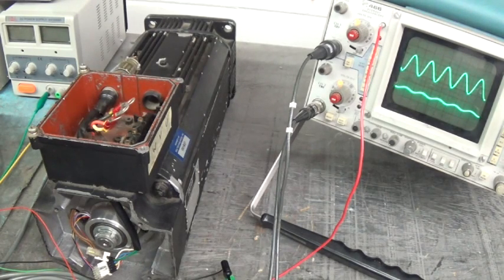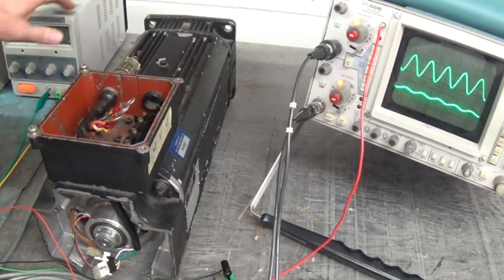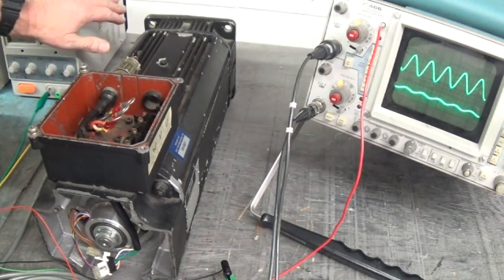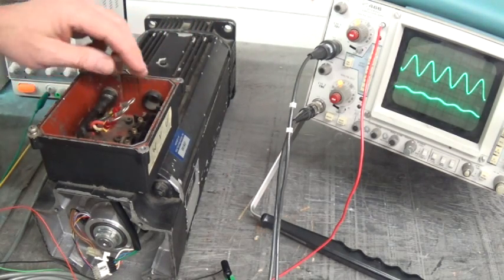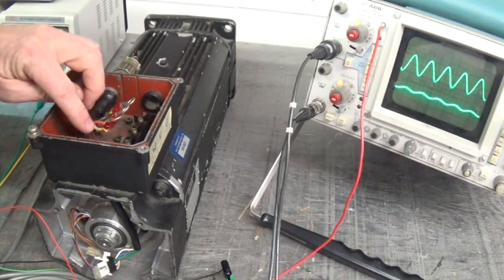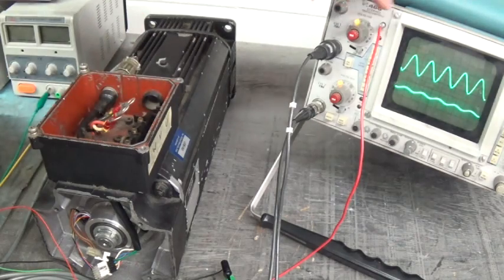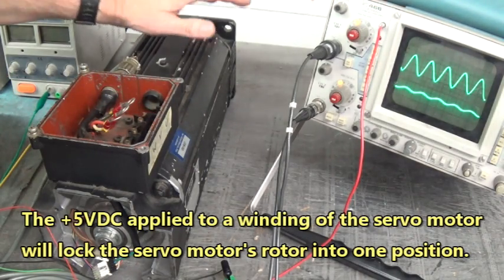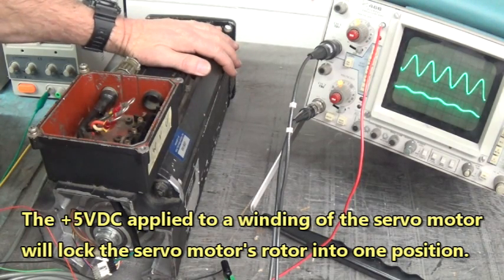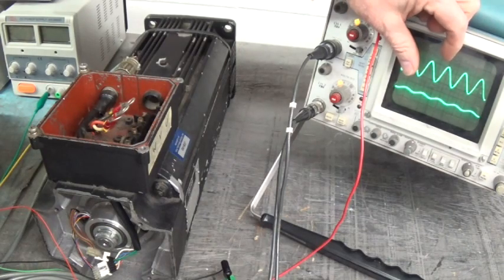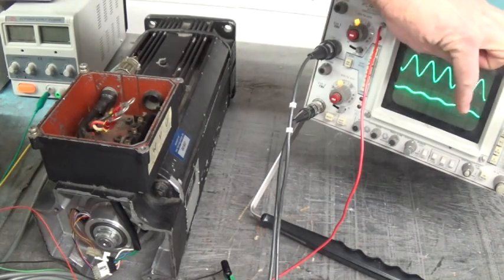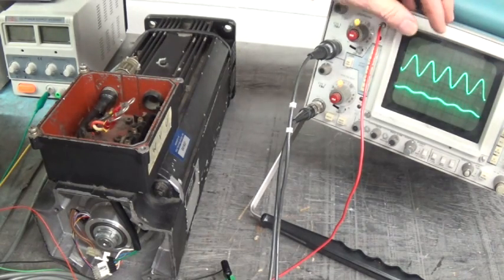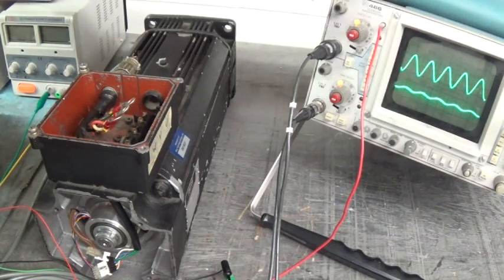So what we want to do is we're going to apply this five volt five amp to the input windings of the motor—the U, V, and W. And we want to find a locked rotor position that will either make the sine max and the cosine flat line, or vice versa, the sine flat line and the cosine at max.